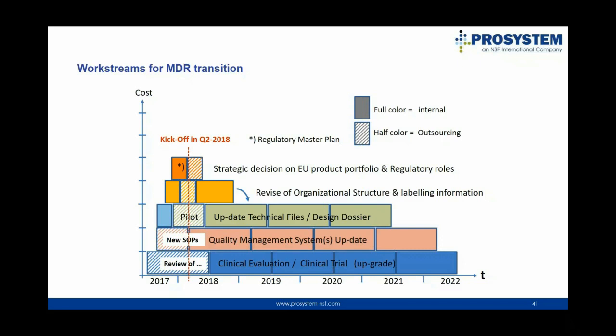To build up a quality management system according to the new MDR regulation, ISO 13485:2016 is a perfect start, but at the level of detail, you have to influence approximately 25 different processes and add requirements from the MDR regulation. If we look into the area of technical files and design dossiers, this is the heaviest work in the long term. We put it here in green.